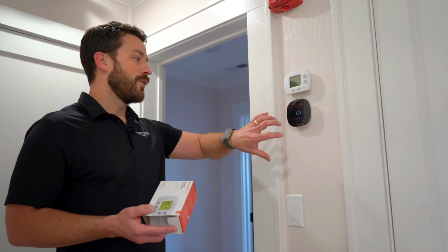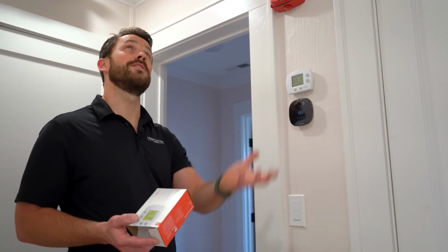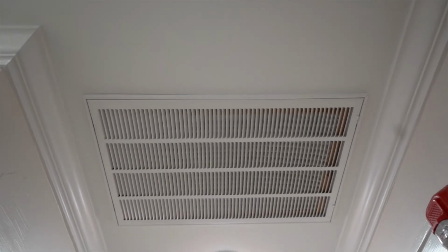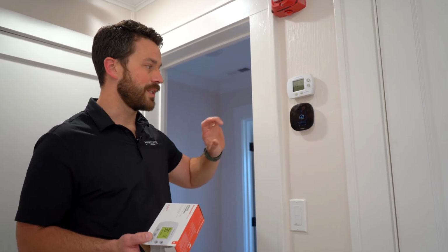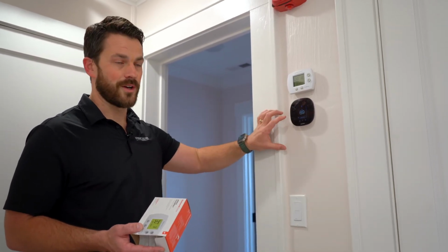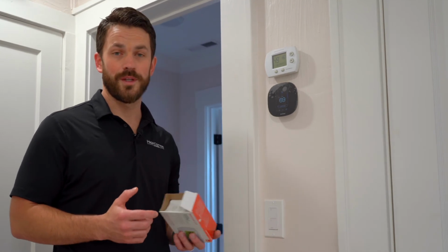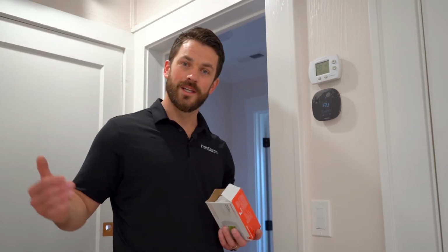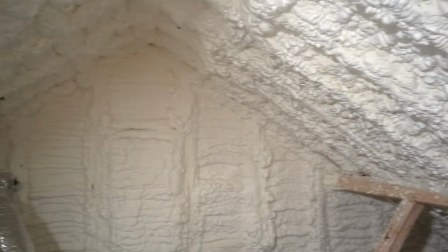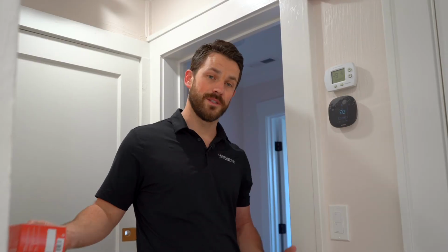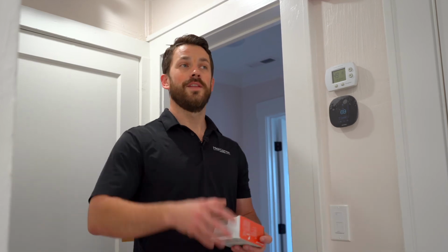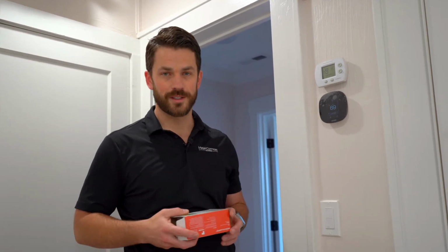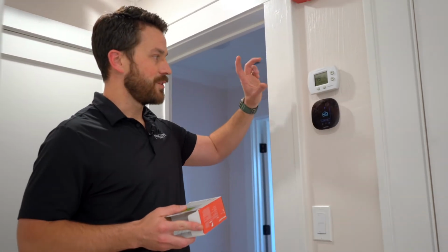The return for the air conditioner is located right above me, which is why the Ecobee thermostat is here in this hallway. There's no dedicated return for the dehumidifier—it just pulls air from the attic. We spray foam the roof deck like we do on a lot of our builds, so it's inside the envelope. It's pulling air from the attic, which is pulling from where we're standing, and supplying it back through a supply duct. So there's no return grill in the ceiling like we have for the air conditioner. We stacked them side by side so it'd be easy to maintain.